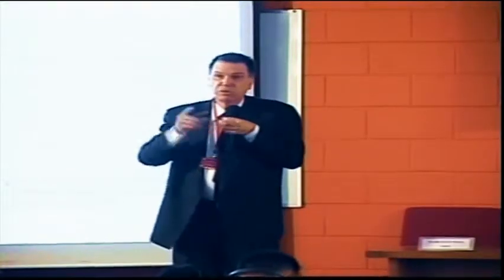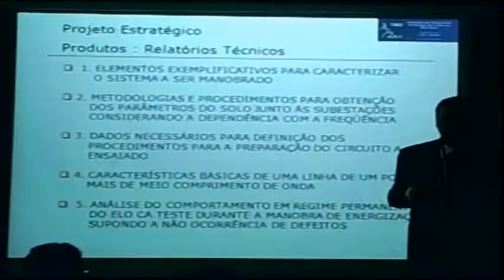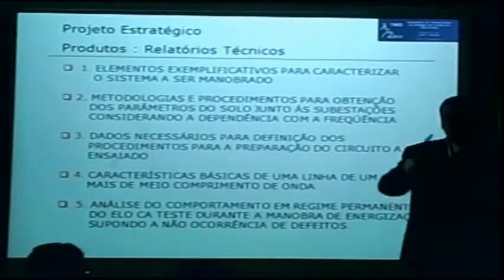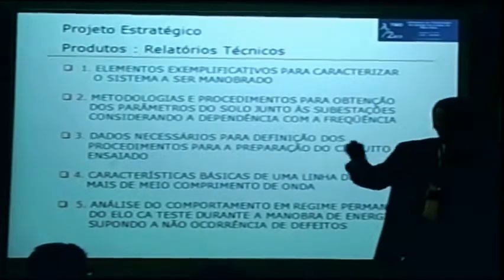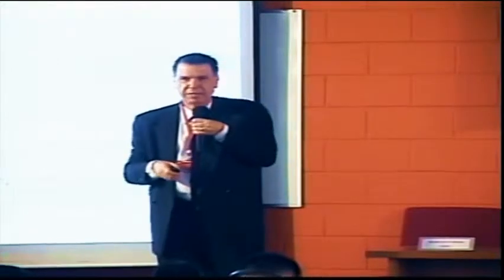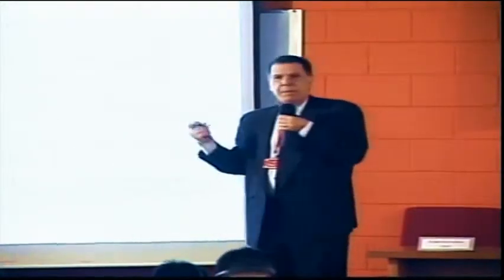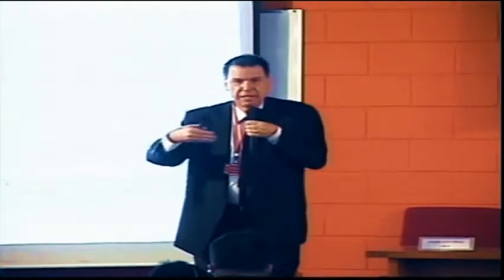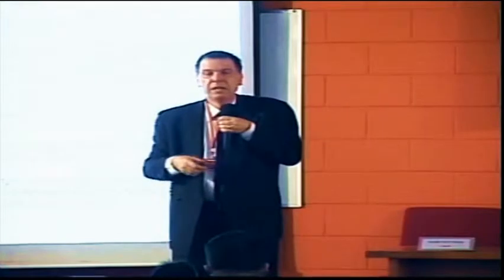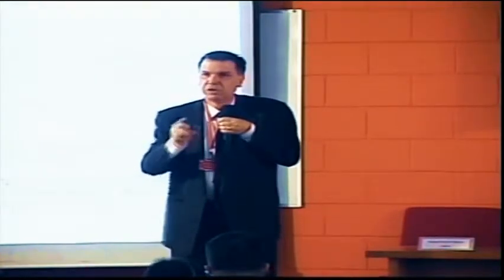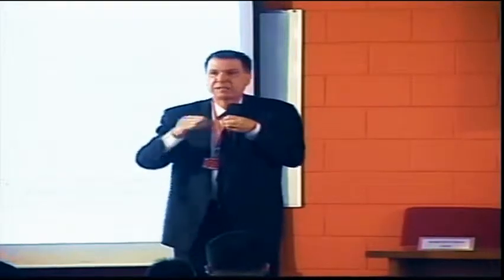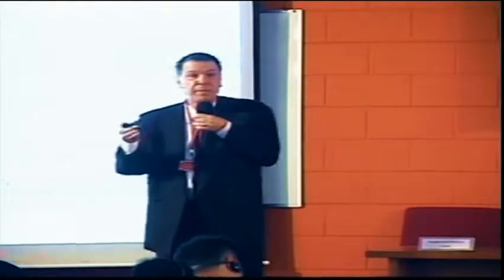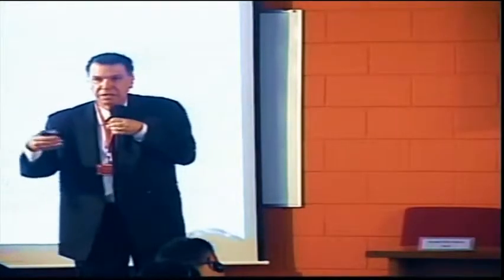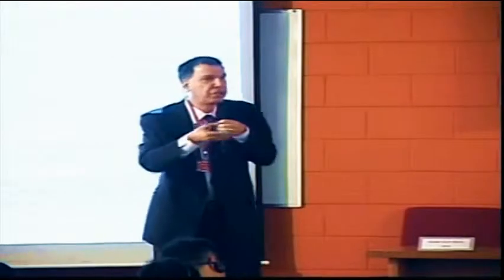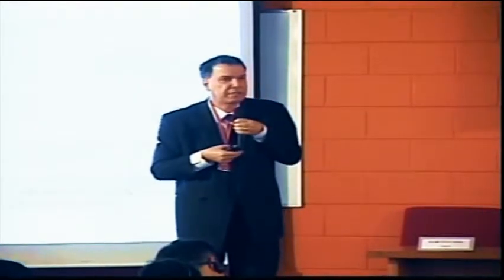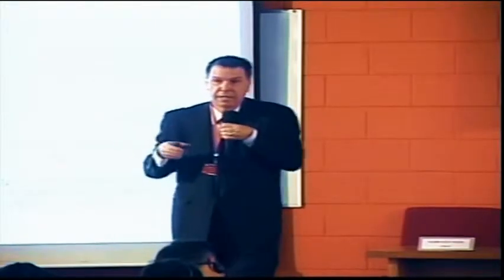These reports cover studies of the permanent regime behavior of the link, and all the energizations conducted with and without faults throughout the line, using the ATP and PSCAD tools. We prepared a report with the data needed to model the system, and a protection study for the entire link, covering single-phase and three-phase faults. This is very interesting because there isn't much written in the literature about protection in half-wavelength lines, so this was a major gain for the sector and for the ANEEL strategic project.